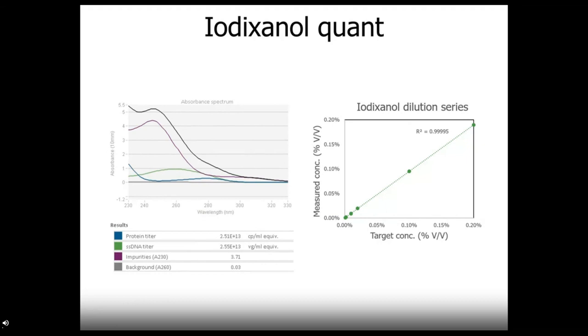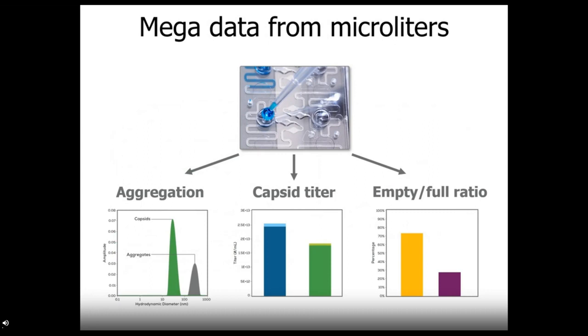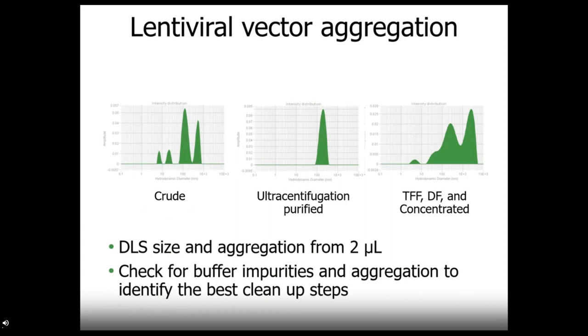And if iodixanol is part of your process, it is useful to know exactly how much is in your sample and to check on the iodixanol concentration after each buffer exchange. Stunner can help out here as well and will detect iodixanol in your sample as low as 0.0005% by volume. So from only two microliters, Stunner combines UVVIS, DLS, and SLS data to tell the whole story about your AAV sample, delivering mountains of data about sample aggregation, AAV full and empty capsid titer, and empty full ratios.